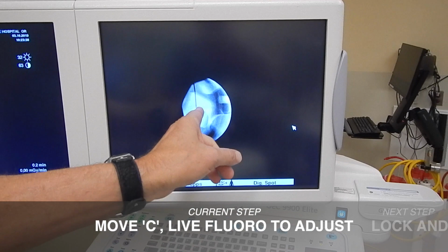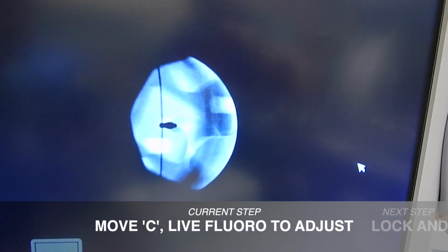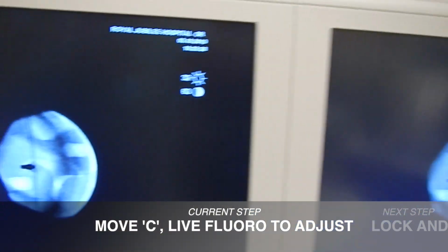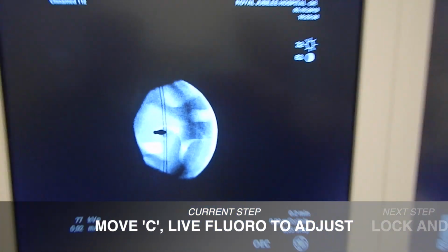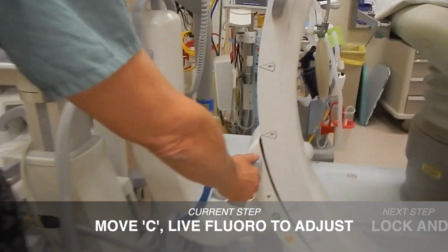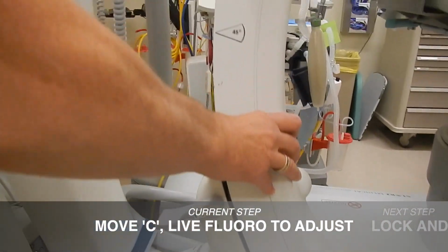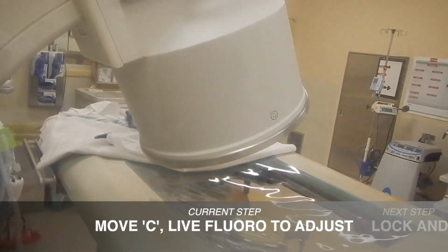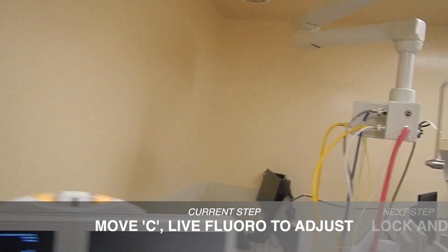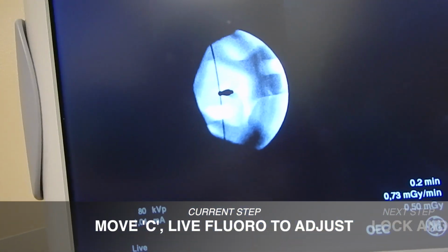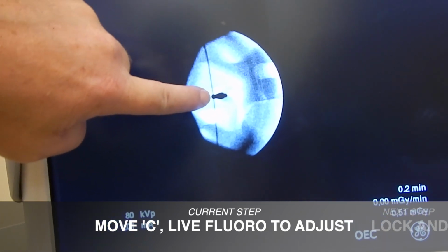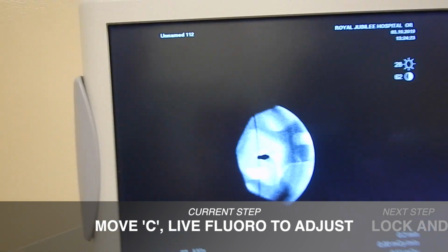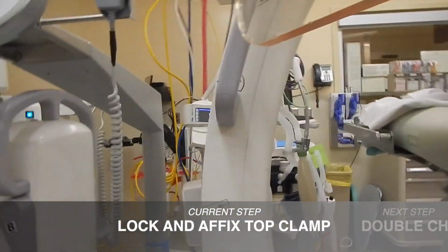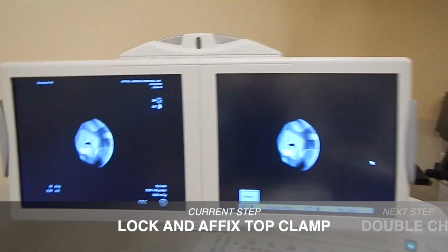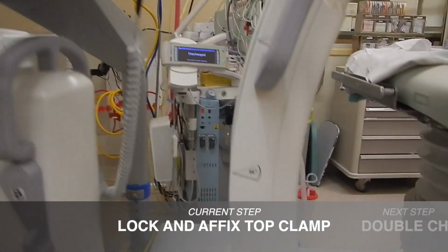So this is how it should look in the axial calibration position. And if you look over here, we just have to make a little adjustment. So I'll show you how to do that. You just take that lock off, and while you're fluoroing, move the C slowly, so the lines go toward the tip of that object, basically as if it's a line going right through the center of a circle. And then you lock it. Always fluoro again after you apply a lock. Sometimes it changes.